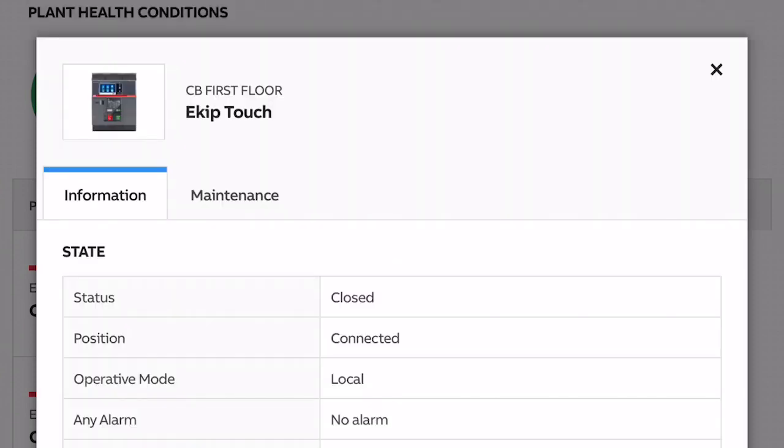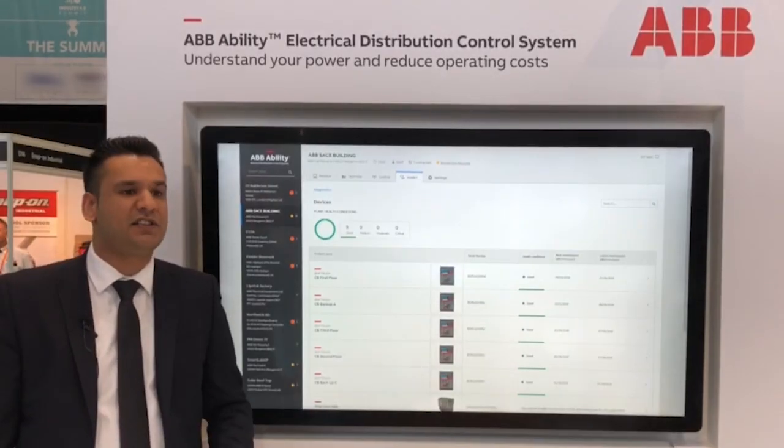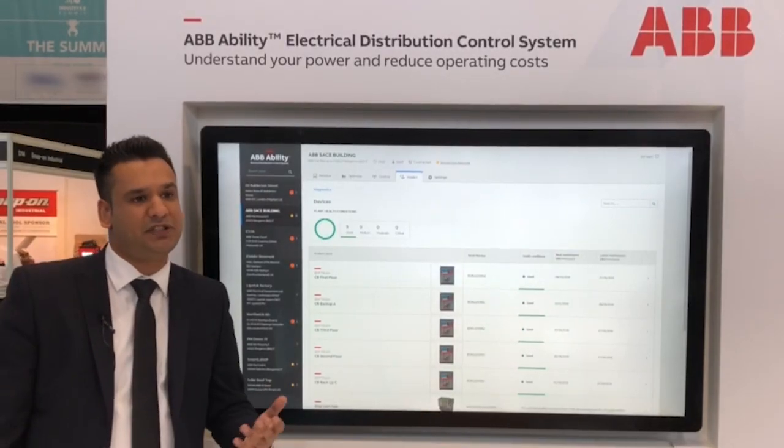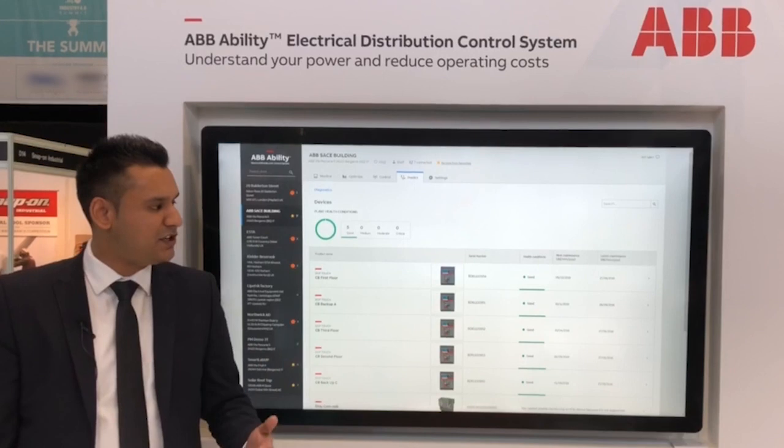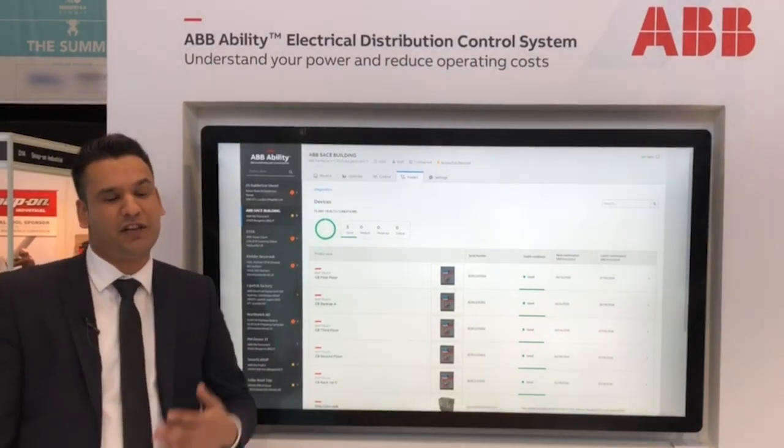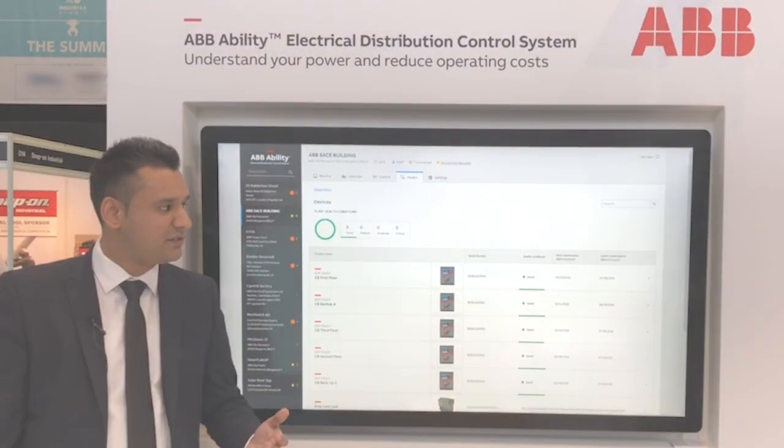With ABB Ability EDCS, we're now moving to predictive maintenance. This gives you a date when the breaker is due to be serviced based on parameters such as temperature, vibration, humidity, and the number of operations.